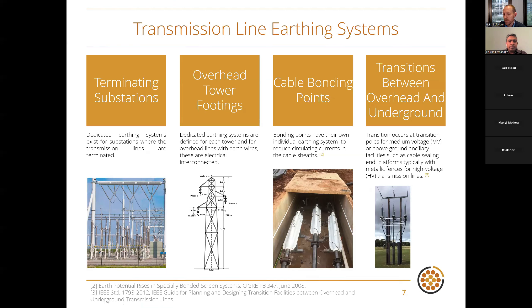Transmission line earthing systems involve many different interconnected systems. At both ends, substations have their own earthing systems interconnected with systems along the line, including overhead tower footings, cable bonding points, and transition locations such as transition poles or ancillary facilities — all of which have their own earthing systems. All of these need to be considered because they are interconnected, and there are complex current pathways during earth fault conditions.